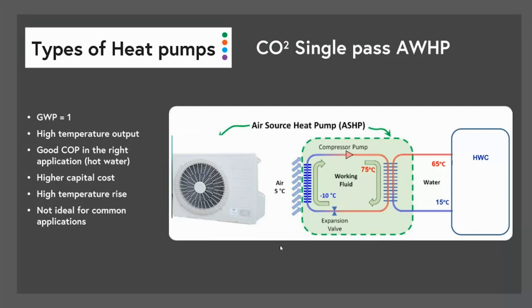They're not ideal for small temperature lifts because they can't do it physically. So they work well under load, but if you had a cylinder that was already, say, 55 degrees and you just wanted to bring it back to 65 degrees, a CO2 heat pump can't deal with that. It can only deal with a low temperature input into it. So it has to be configured correctly.